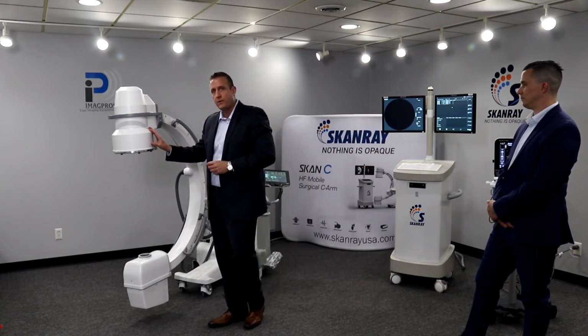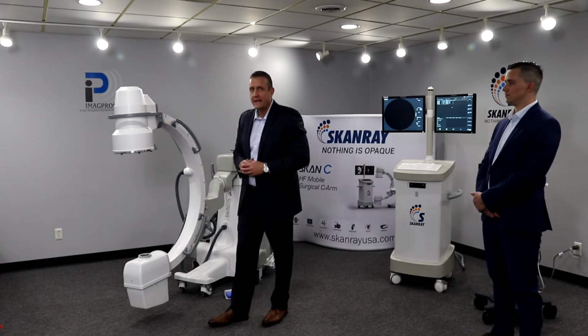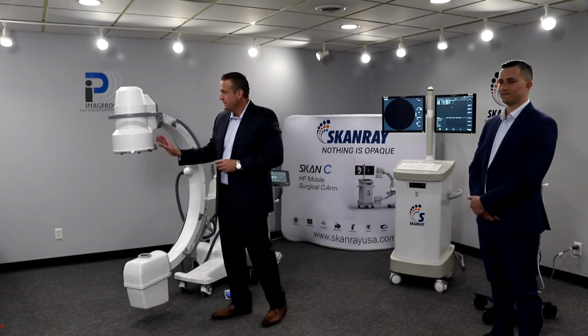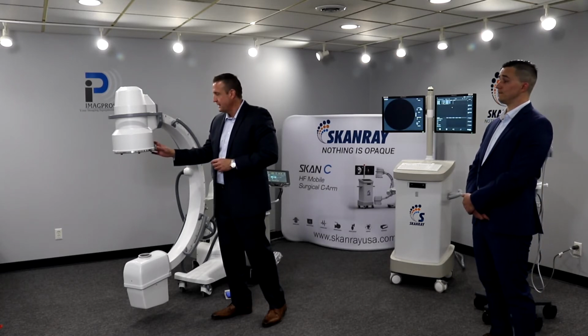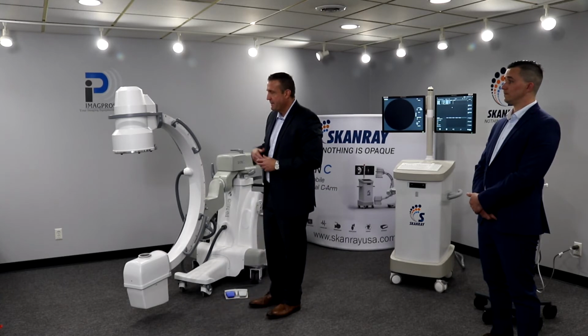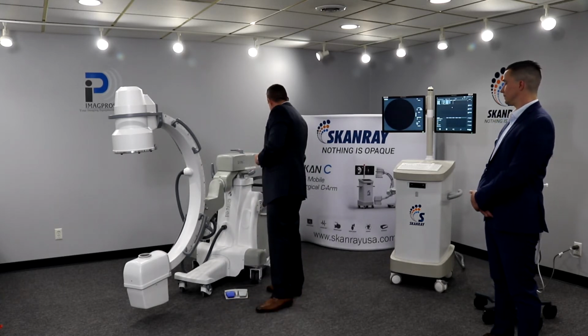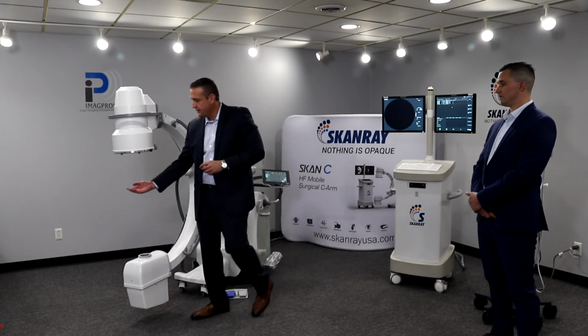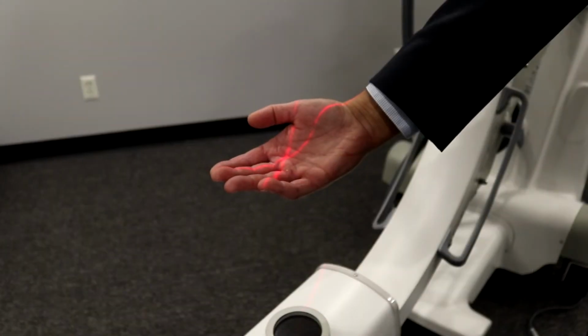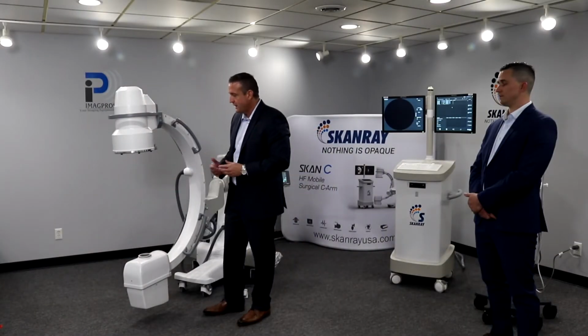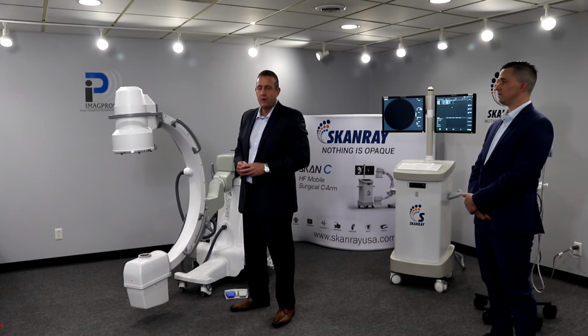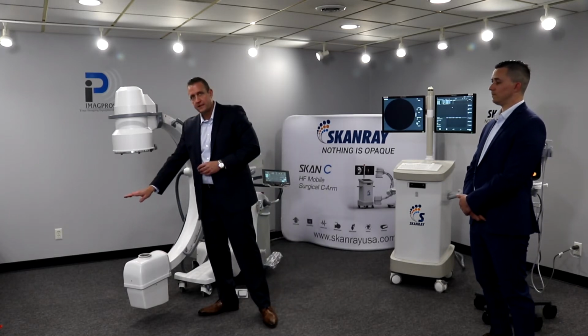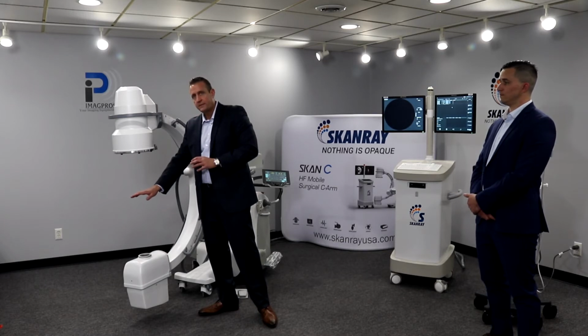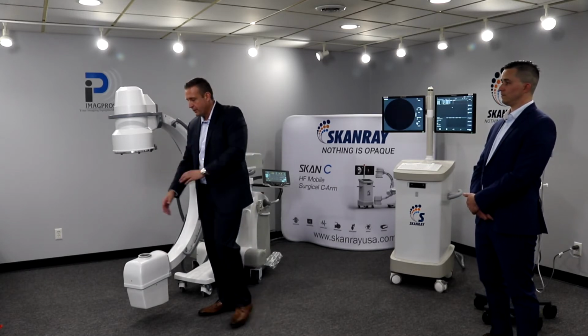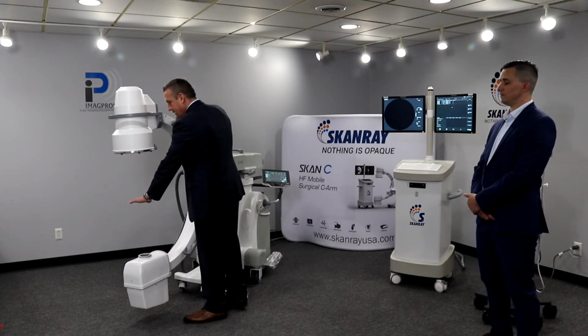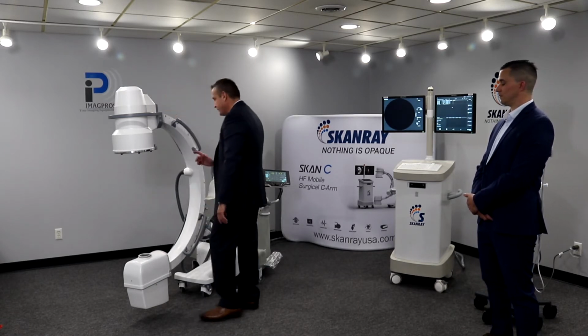This is a Toshiba II with a Canon camera. It's one of the best IIs you can get on the market. It does have a built-in laser. It's not battery operated. It's fully within the system, so it's not battery power. You don't have to worry about replacing batteries. If I go to the laser, it's a class 2 laser. It's very bright. So when you have operating lights, it's very distinctive. The nice thing about this is it's also in line with radiation control. When you don't have a laser and you don't have a positioning starting point, you don't know exactly where the beam's at. So you might have to take a few shots to get into the spot. With this one, you're going to limit the amount of shots you have to take for the exposure. Okay, so that's a really nice feature on the system.